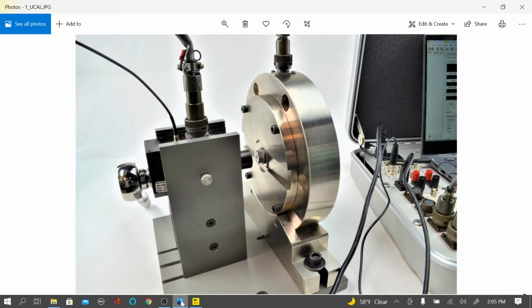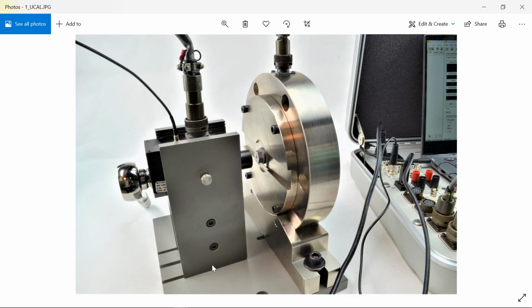In this video, I want to show you an alternative method of calibration of the ultrasonic bolts. Some of our users want to collect information from load, ultrasound, and torque value at the same time. The previous method that I showed you was collecting data from ultrasonic and load. Then you would combine them together and come up with the average calibration curve.